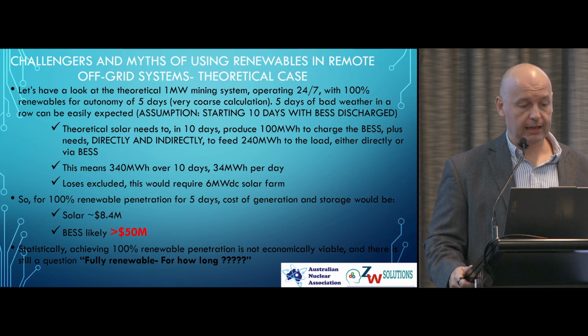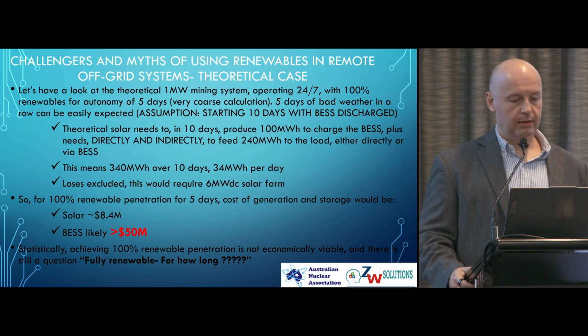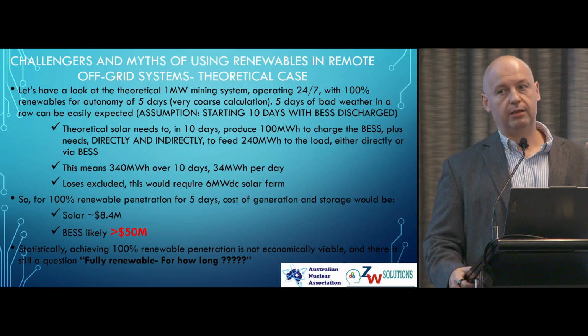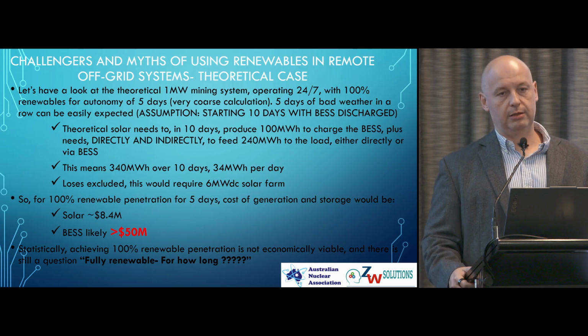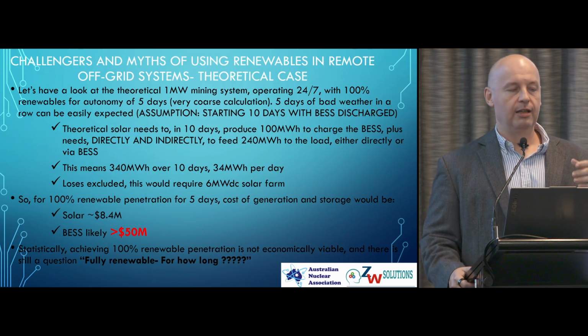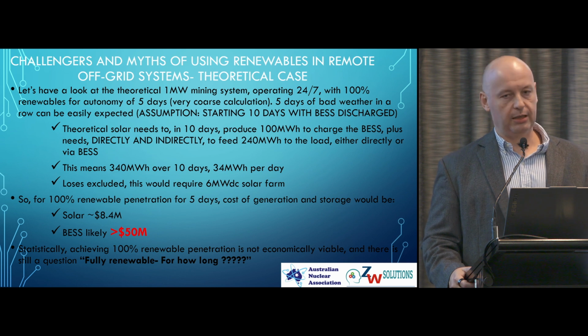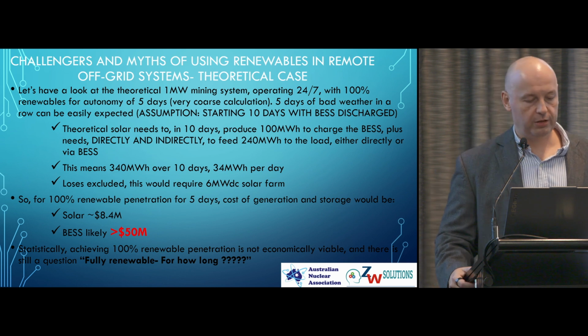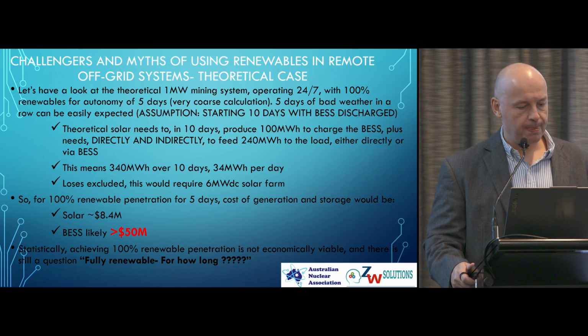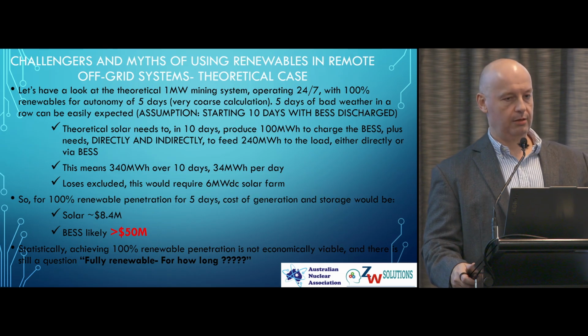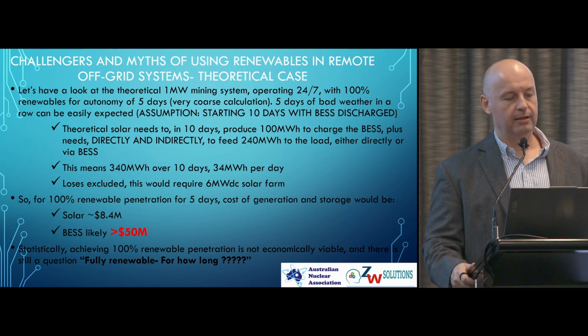So if we look at the solar, we would need 100 megawatt hours to supply the battery and 240 megawatt hours to supply the load. So we need 340 megawatt hours roughly. To do that, we need about a 6 megawatt solar farm. So 6 times the size of the load. 6 times.